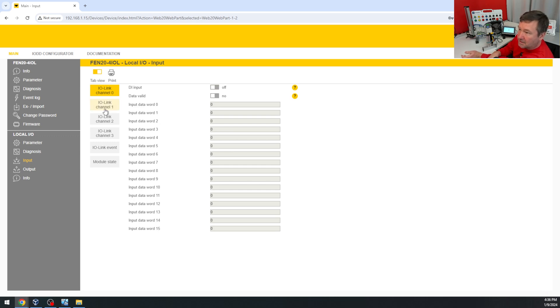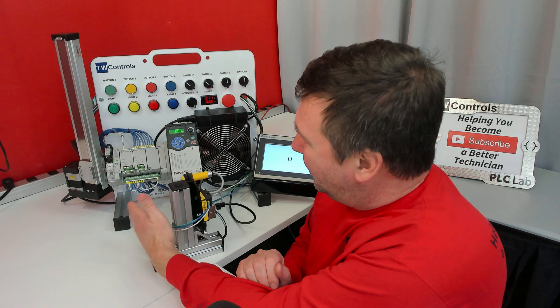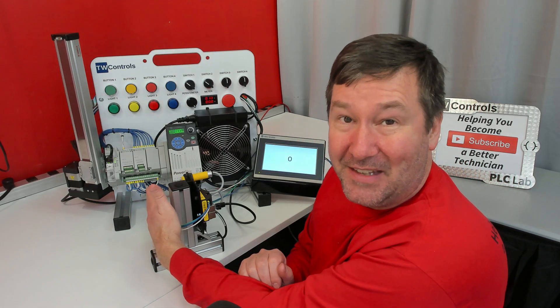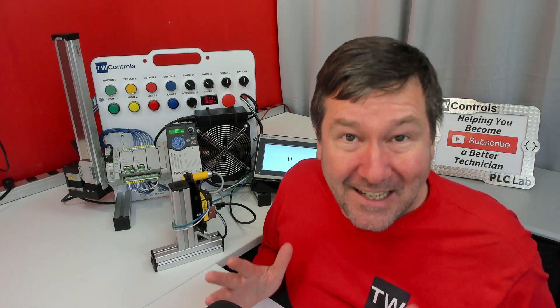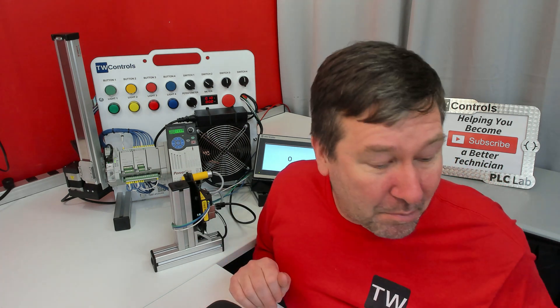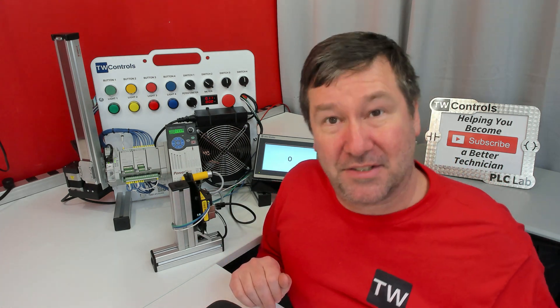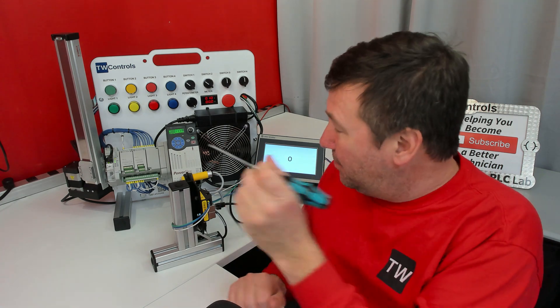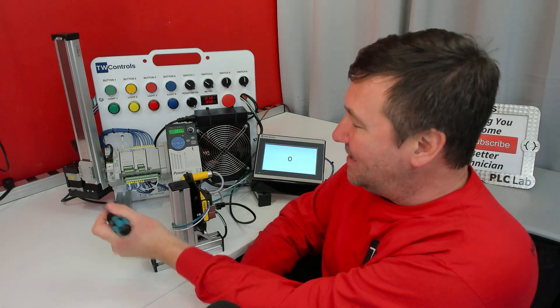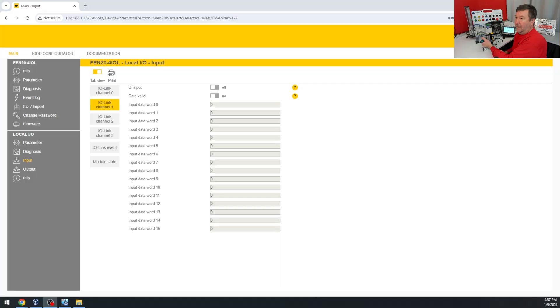I can go to channel one, and if you stick your hand over it, it's not going to work because it's an inductive prox switch. So we need something metal to put over it to test it with, and when I stick the screwdriver over it, it's switching.